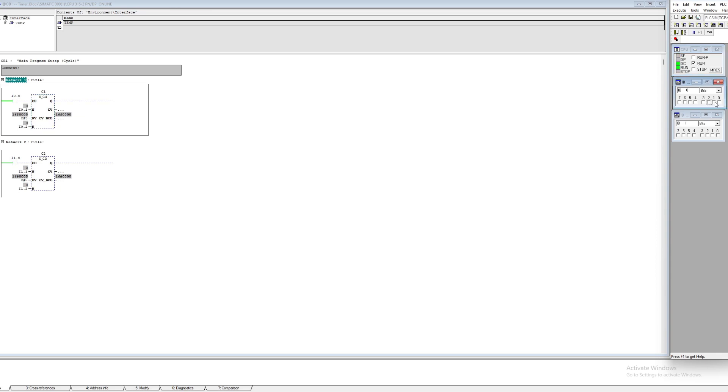As you can see if I trigger the S input it will set the block's value to five. Else if I trigger my CU input it will count up by one for each time I trigger it. And the R input will reset the block back to zero.